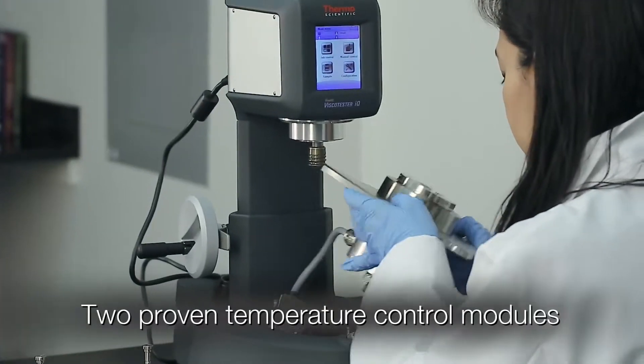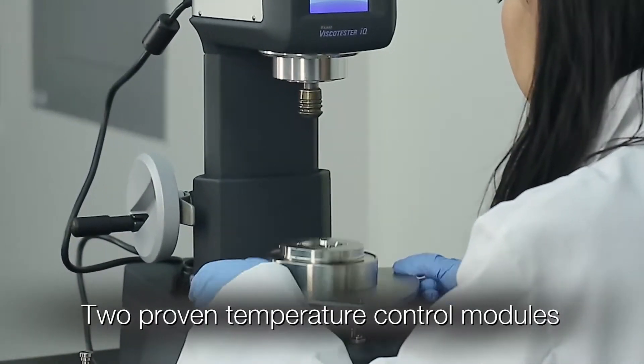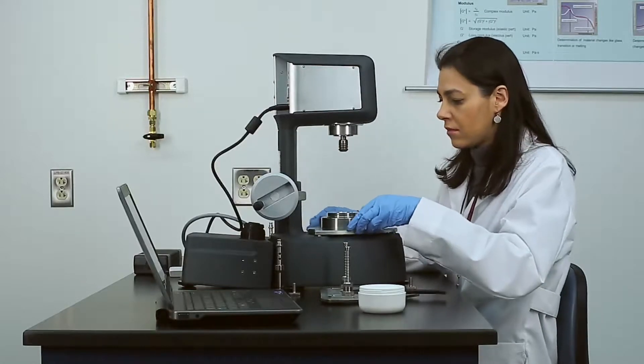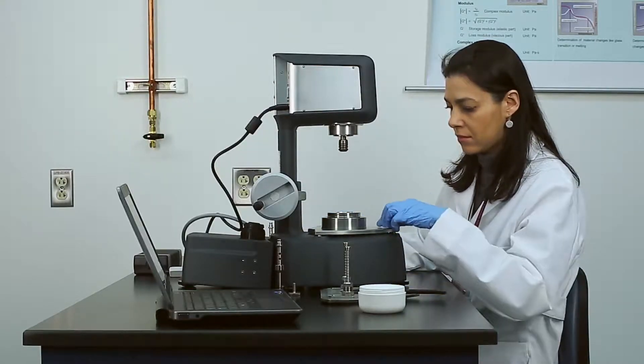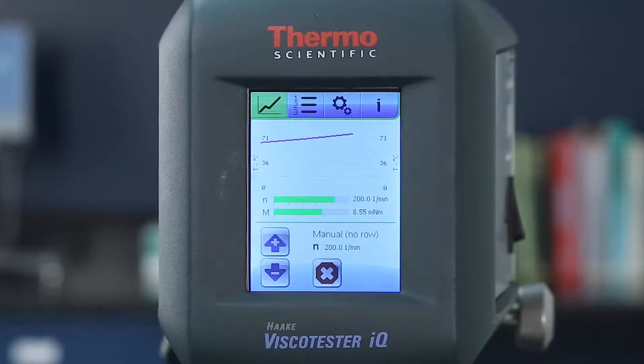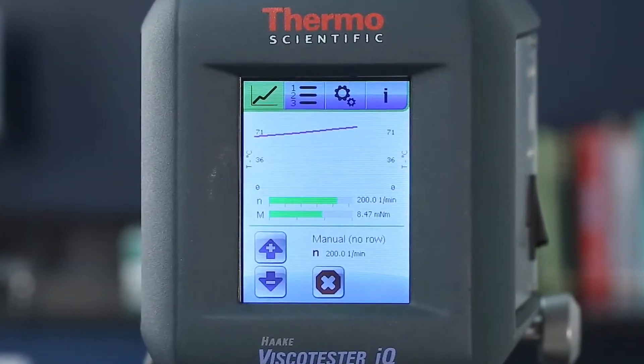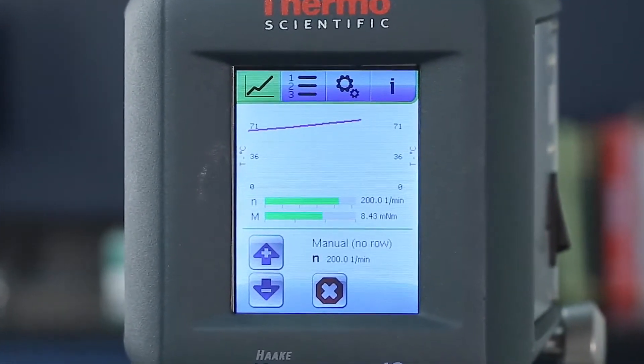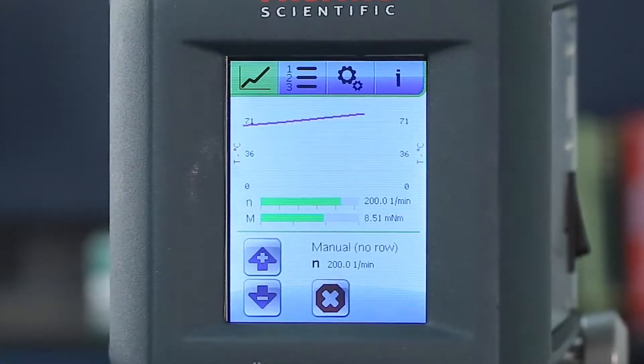Two modules are available for reliable temperature control, including a self-contained Peltier controlled unit. For maximum temperature range, the liquid controlled module spans minus 20 degrees Celsius up to 180 degrees Celsius.